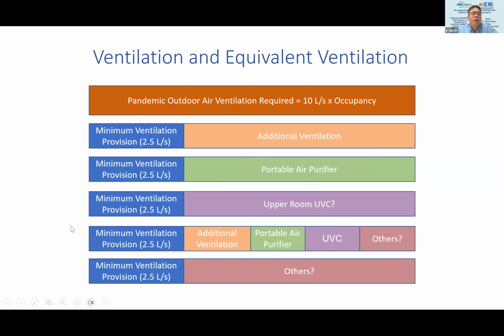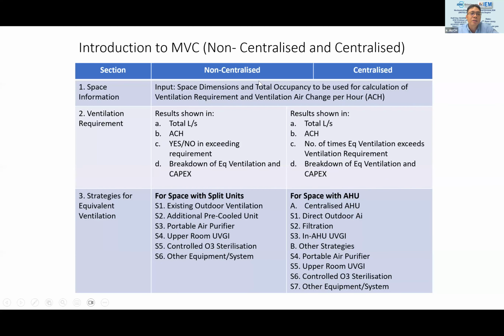No amount of filtration can totally replace ventilation. That's why we encourage people to have a minimum prescriptive bylaw requirement. And then you add on additional ventilation, or purely portable air purifiers or UVC and so forth. So the MVC has this strategy concept in mind: what is the minimum ventilation you can provide? What is the quantity of portable air purifiers that you are providing? You add these up, and where do you stand in comparison to the 10 liters per second? So as a summary, this is how it looks.